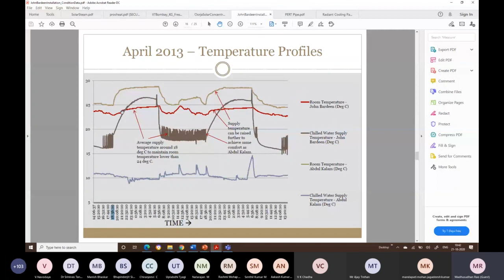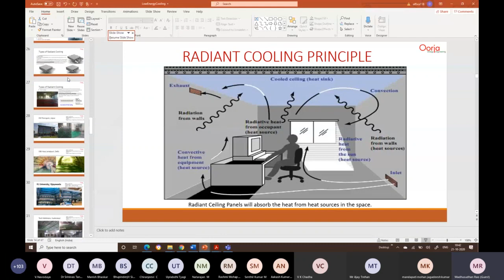The second question is about the condensation. If we are maintaining a temperature of 24 degrees and 50% RH, which is the typical temperature that is maintained, as I mentioned many times, the floor surface temperature is only about 20 or 22 degrees centigrade. Most cases it is 22 degrees centigrade. The dew point, if the air is at 24 degrees 50% RH, is 13.5 degrees centigrade. So unless the surface temperature is 13.5 or lower, condensation will not happen.